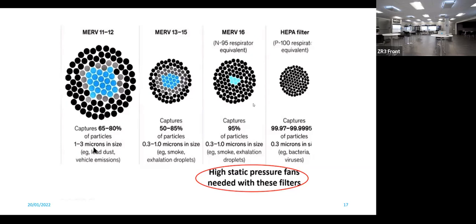And if you do a lot of reading on HEPA filters, it will always talk about 0.3 micron in size. That's because that's the testing they do. They test all the efficiency of filters on particles the size of 0.3 microns, because that ends up being the most penetrating particle size. So that's actually the particle that will break through the HEPA filter first. It actually becomes more efficient for smaller particles and obviously more efficient for larger particles.